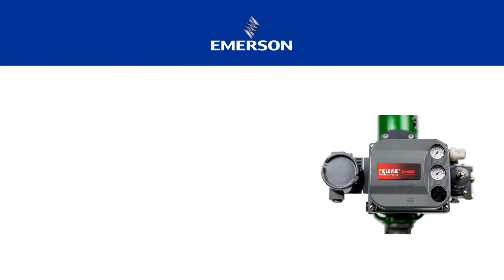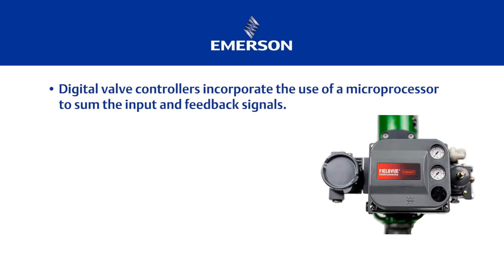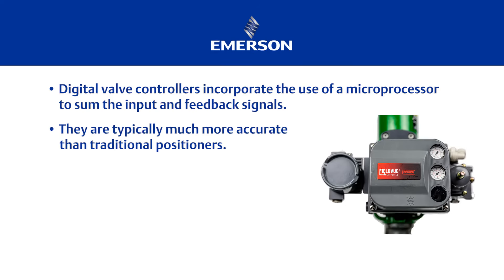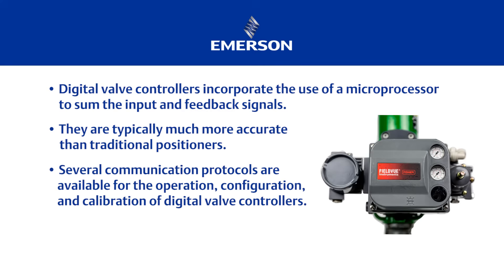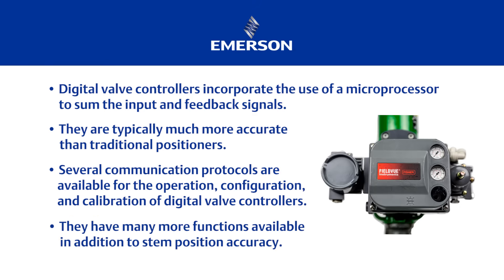Here are some things to remember about digital valve controllers. Digital valve controllers incorporate the use of a microprocessor to sum the input and feedback signals. DVCs are typically much more accurate than traditional positioners. Several communication protocols are available for the operation, configuration, and calibration of digital valve controllers. And digital valve controllers have many more functions available in addition to stem position accuracy.